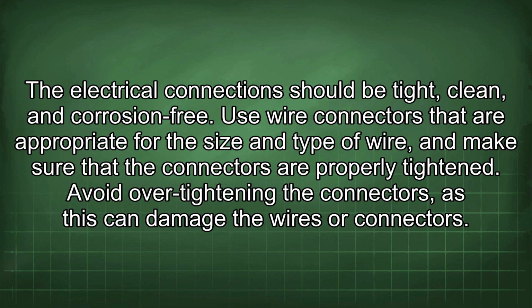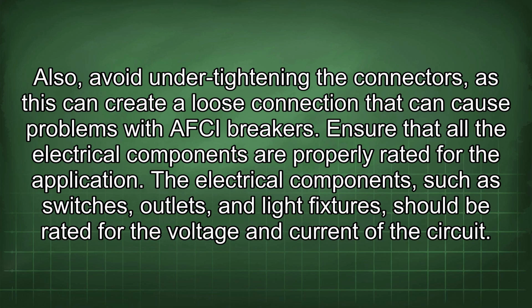The electrical connections should be tight, clean, and corrosion-free. Use wire connectors that are appropriate for the size and type of wire, and make sure that the connectors are properly tightened. Avoid over-tightening the connectors, as this can damage the wires or connectors. Also, avoid under-tightening the connectors, as this can create a loose connection that can cause problems with AFCI breakers.